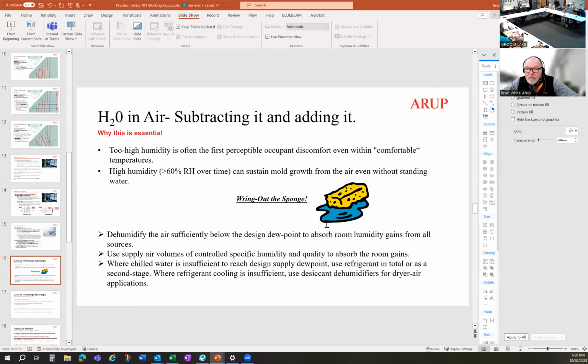So you only have an 8-degree split across that design coil? Correct. Yeah, with a typical, well, let's put it this way. With a chilled water coil, if you're using 42 or 44 degree chilled water, and obviously reverse flow, you can do it with 40, 42 or 44 degree chilled water and a 12 or a 14 degree delta T. With refrigerant, your cooling coil temperature, your saturated suction temperature is going to be somewhere down around 40, maybe a little lower.